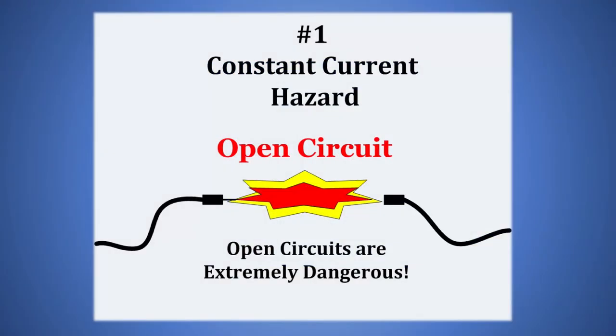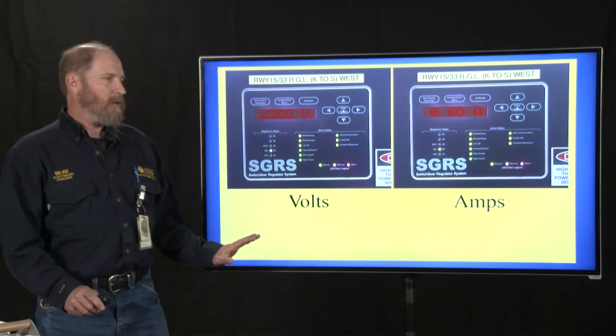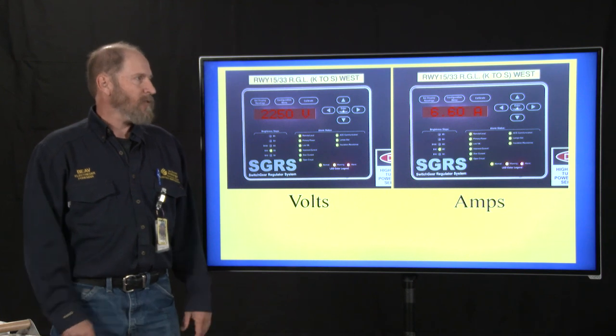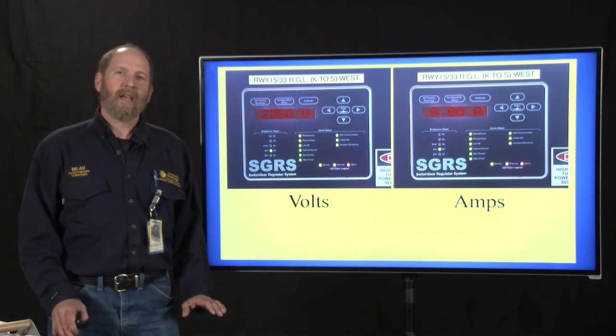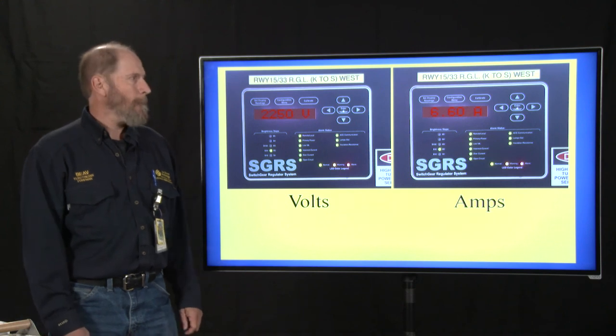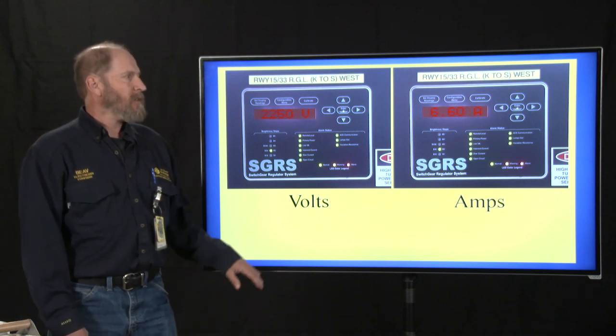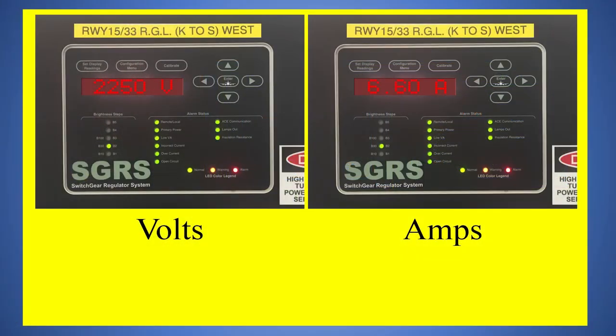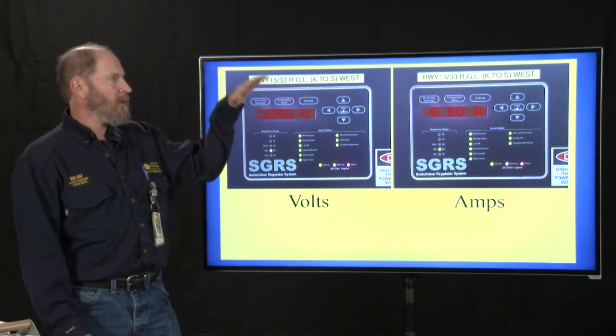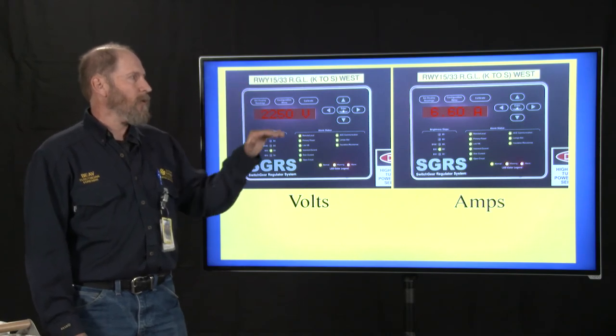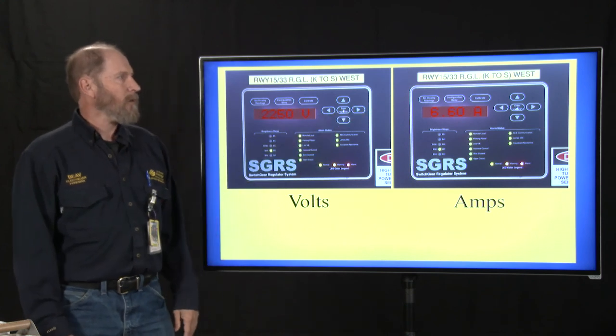Really, one of the biggest dangers with constant current is the open circuit. Okay, so in order to understand how dangerous it is to have an open circuit, you have to understand how a regulator works, okay? A regulator's job is to maintain a constant amperage across this lighting circuit. It does that by varying the voltage up and down in order to push the right amount of current through that wire. Now, a lot of people don't understand amps and volts, so I'm going to put this a little different way in order to kind of help you.